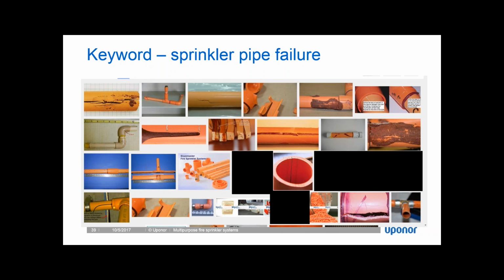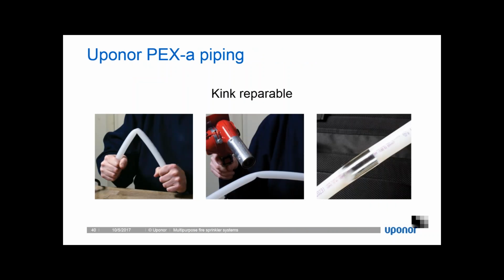So Uponor Aquapex tubing is durable. We have a thermal elastic memory, which we use to make our connection systems. And that shape memory is also very important when you're doing an installation. If you do an installation like I do, you're bound to get kinks, because I work too fast and sometimes I cut corners, and cutting corners causes kinks in the pipe. But lo and behold, I can take a heat gun to that pipe and repair it. You cannot do that with CPVC, or actually most other PEX materials.